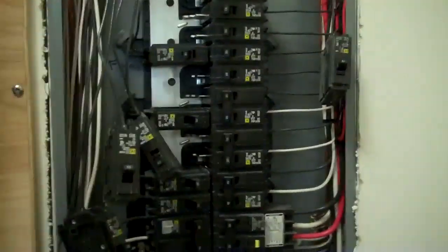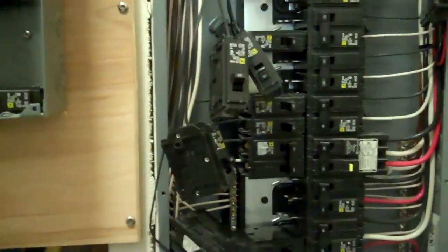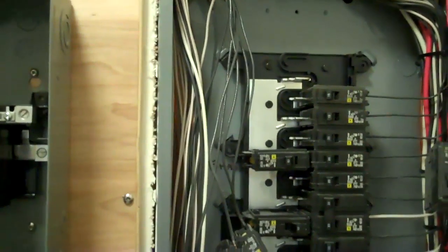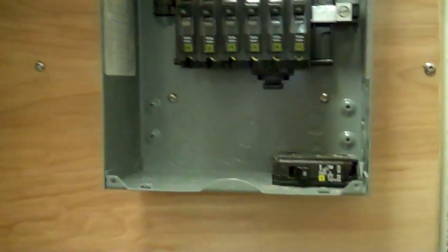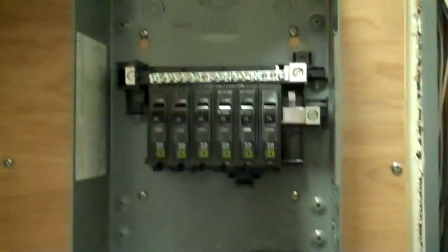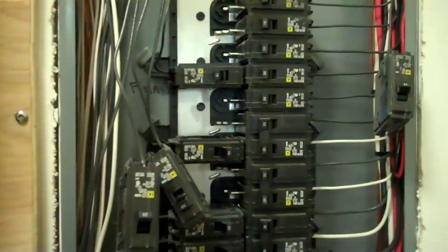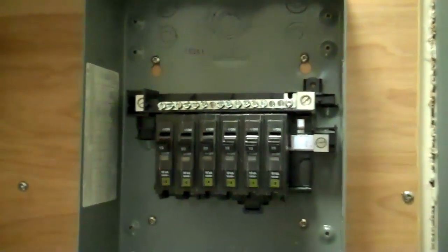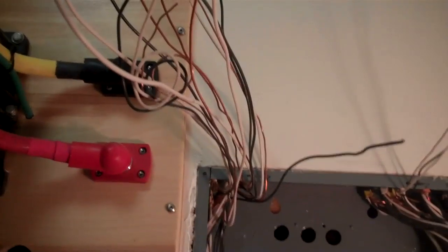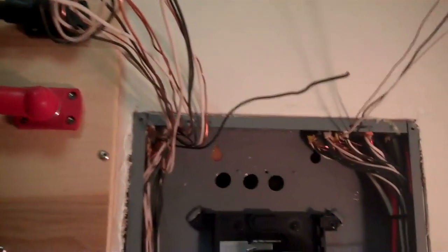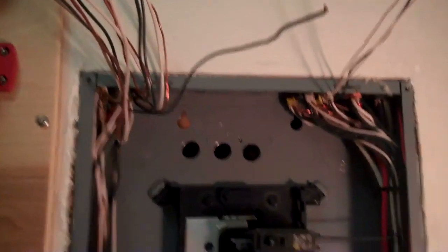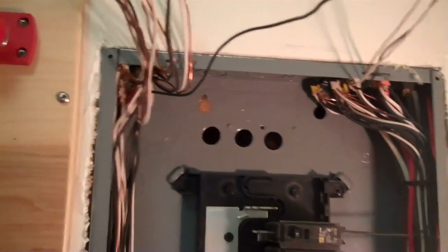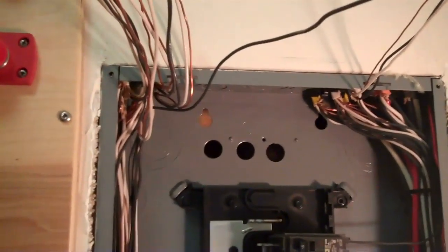These are the six circuits we've taken out, basically it was living room receptacles which is some lamps, the master bedroom, the master bath, a half bath, the one sticking up there, that's the refrigerator. What we're going to do is wire nut all these together in the panel, which is legal, and then we're going to run six pieces of number 12 to this row of six breakers. And we're going to set a 30-Amp breaker in here, and it's going to run this sub-panel. You might think the 30 might not be enough to run all these circuits, but when you figure what all's on. All these circuits are separated out, we're going to move them over to the sub-panel. The way we're going to do that is we'll just wire nut them right here in the panel. As you see, I drilled three holes in the back there. I'll feed the wires around the back through a Romex connector, and we'll hook it all up.